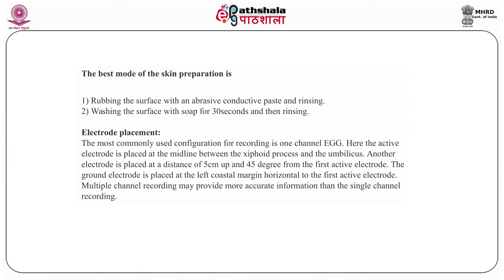Now, the placement of electrodes. The most commonly used configuration for recording is one-channel electrogastrography. The active electrode is placed at the midline between the xiphoid process and the umbilicus. Another electrode is placed at a distance of 5 cm up and 45 degrees from the first active electrode. The ground electrode is placed at the left costal margin horizontal to the first active electrode. Multiple channel recording may provide more accurate information than single channel recording.